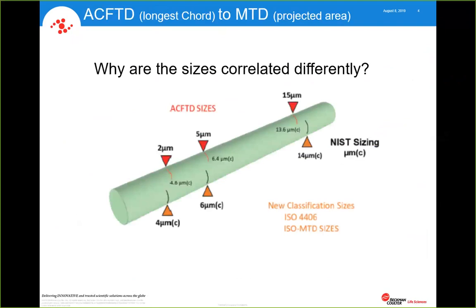If you look at the 4 micron(c) channel in relationship to the ACFTD sizes, it was really close to about 1 micron. So the original 400 sensors, or the current 400 sensors, do not have the sensitivity required to perform the MTD calibrations. What we did when we created the HR-LD100 sensor is optimize the sensitivity of the low end so we can get good resolution down around the 4 micron(c), which equated to about a 1 micron old sizing. You can see that in this diagram, where the 4 micron(c) channel size is actually smaller than the 2 micron. So it's around 1 micron, a little bit larger.